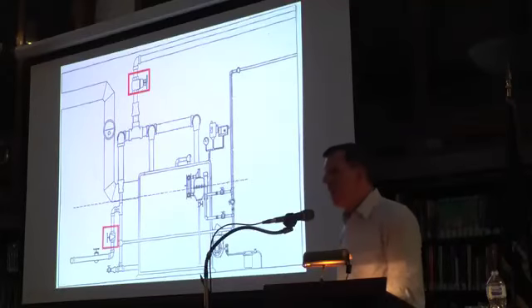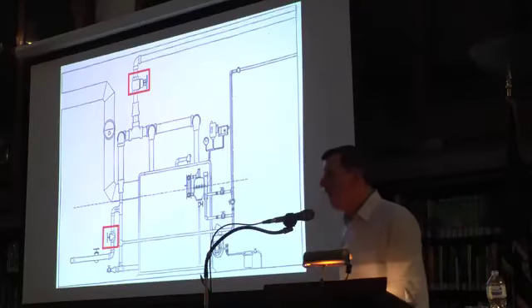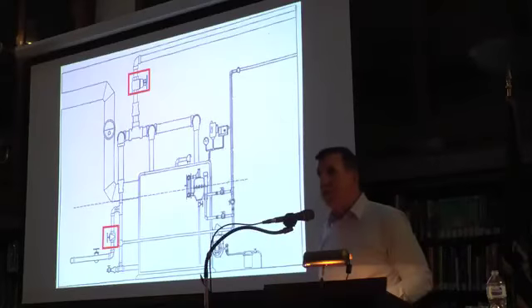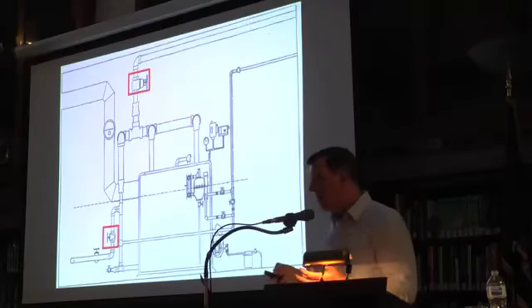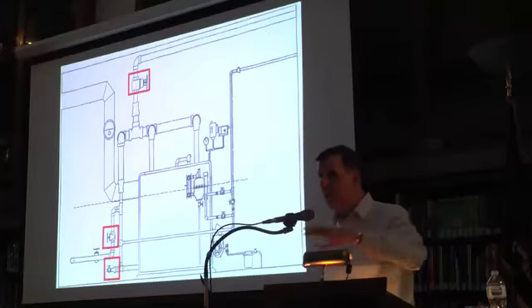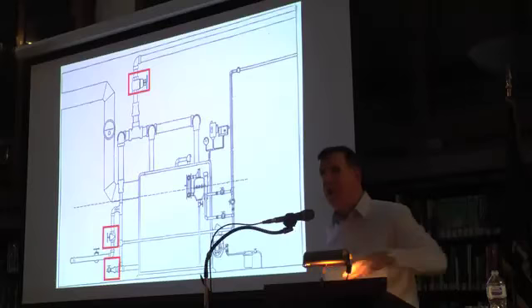Up here we've got a valve that a good steam contractor will tell you you need a king valve. It's not a special valve, it's just a gate valve or a ball valve, a big butterfly valve, say a ball valve, that goes up there on the supply side, and another valve on the return, so that once a year we can close those two valves and isolate the boiler from the system, turn the burner on, bring up about 10 pounds of pressure, and then open that valve that's on the bottom of the boiler. It's going to take all the crap that built up in the boiler and what's called the mud leg of the boiler, appropriately named, because it fills up with mud, which is the metal that's coming down from the system, and it blows it out of the boiler.